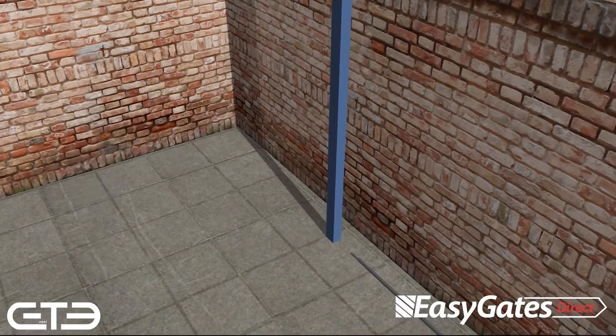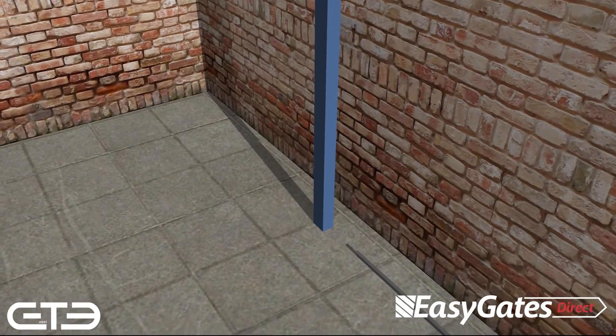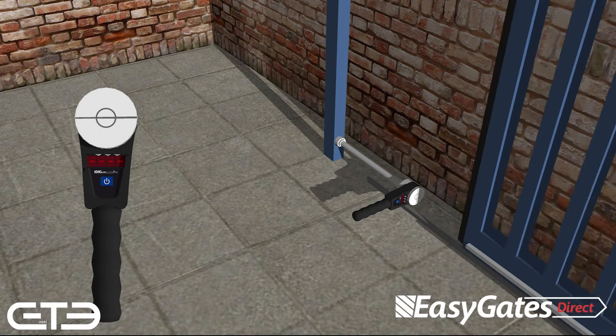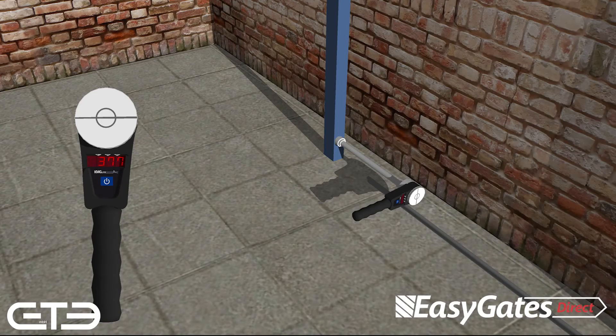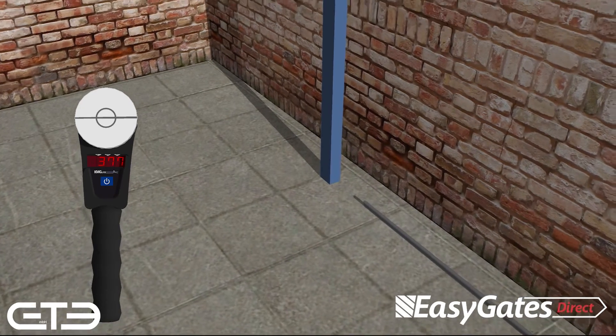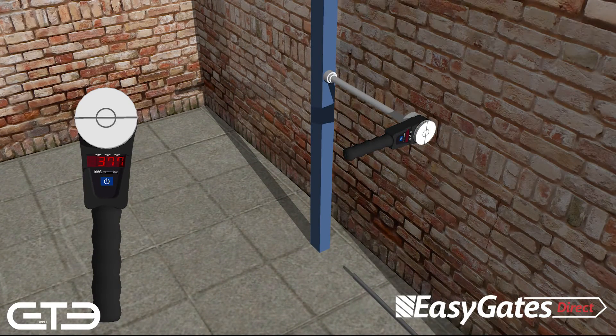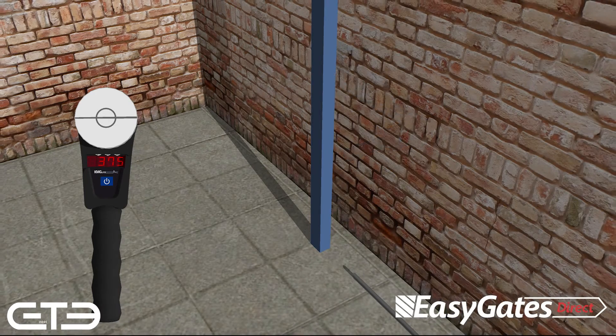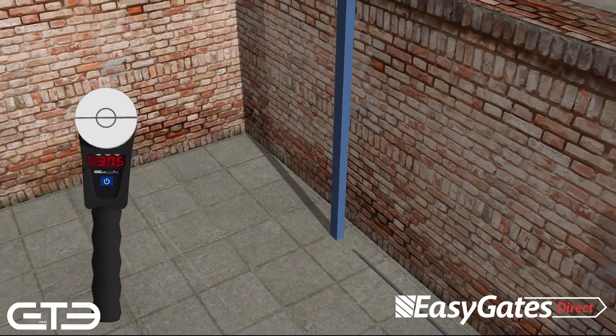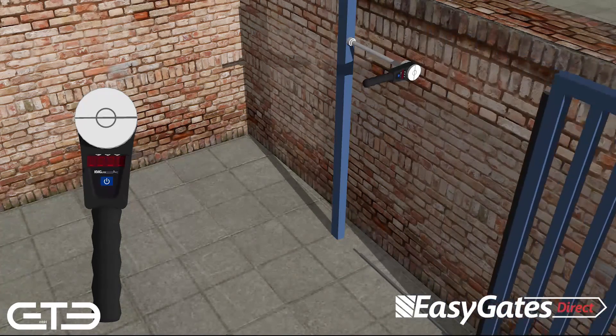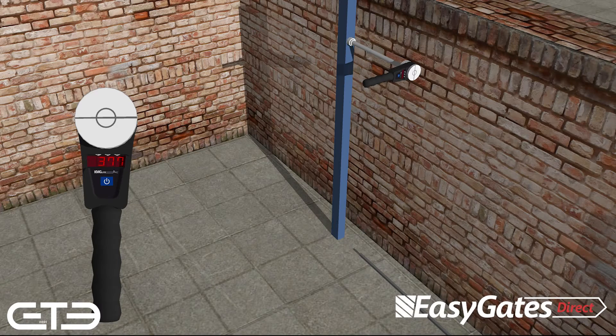For the last set of sliding gate tests, attach the second extender to the instrument and place the extender against the stop post to take your 18th reading. Place it 50mm up and 500mm across. Initiate and test three times to gather your results for an average. Repeat for the halfway up, 500mm across position. Assign your averages a pass or a fail according to the guidelines of EN12453 and EN12445.